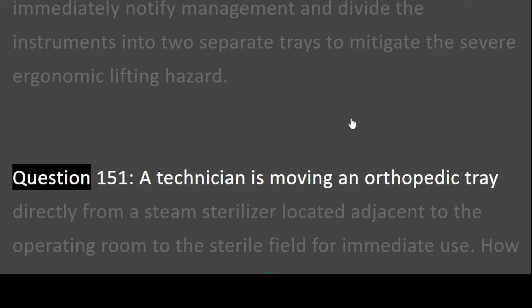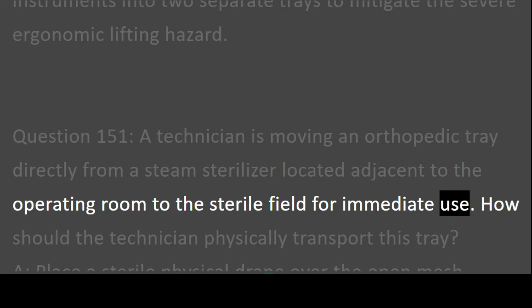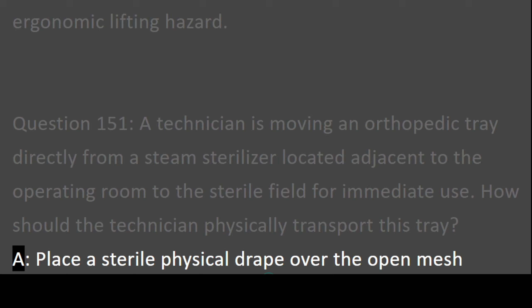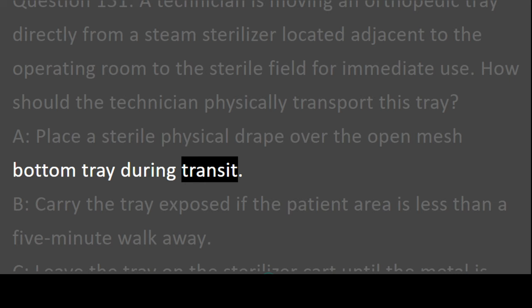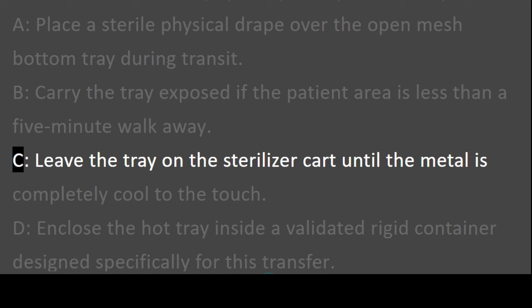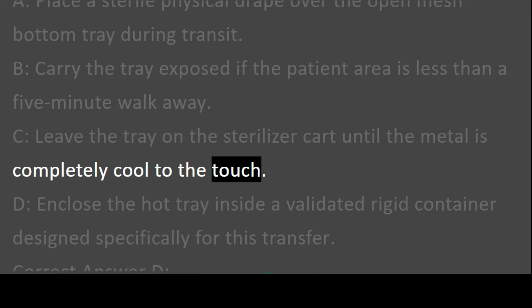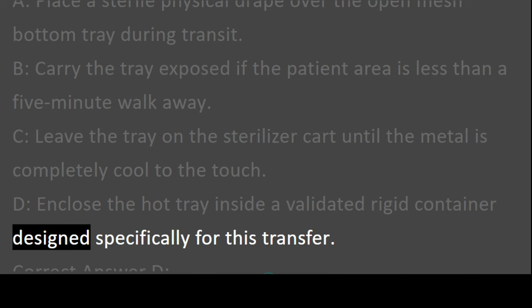Question 151. A technician is moving an orthopedic tray directly from a steam sterilizer located adjacent to the operating room to the sterile field for immediate use. How should the technician physically transport this tray? A. Place a sterile physical drape over the open mesh bottom tray during transit. B. Carry the tray exposed if the patient area is less than a 5-minute walk away. C. Leave the tray on the sterilizer cart until the metal is completely cool to the touch. D. Enclose the hot tray inside a validated rigid container designed specifically for this transfer.